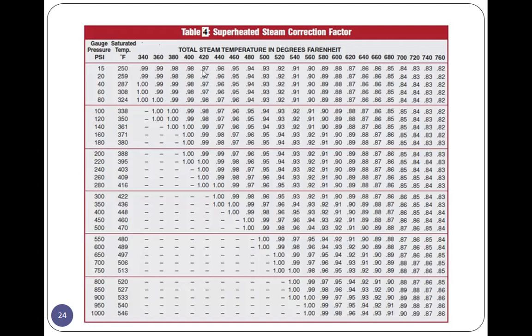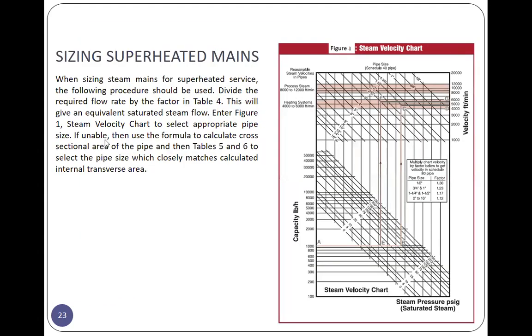This is table 4, the superheated factors, steam correction factors. The total steam temperature in degrees Fahrenheit is not the superheat but the actual temperature. For saturated conditions at 20 PSI, the saturation temperature is 259 Fahrenheit. So at, for example, 420, the factor is 0.97. So you divide the flow rate by it. This will give an equivalent saturated steam flow. Now enter figure 1, the steam velocity chart, to select the appropriate pipe size.